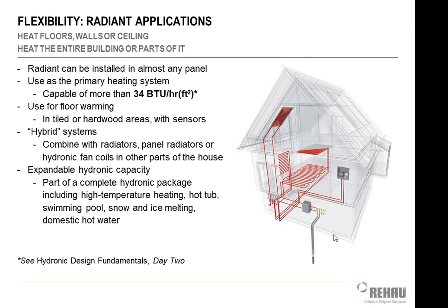You can use the radiant heating system as your only, or as your primary heating system, if you will. Those work best with the concrete systems. If you're going to do it on the wood, you're probably just going to be warming it, and then you're still going to have a heat pump or a furnace or something like that to supplement it, or maybe some radiators off the same boiler kind of thing. Sometimes we'll call that a hybrid system, where we'll have radiant floors tempering spaces that have cold floors, cold wood and tile floors, but then we'll also have some kick space radiators and things like that in other parts of the house by the perimeter. Concrete, you don't have to worry about it. You'll be able to heat the whole house with the concrete.